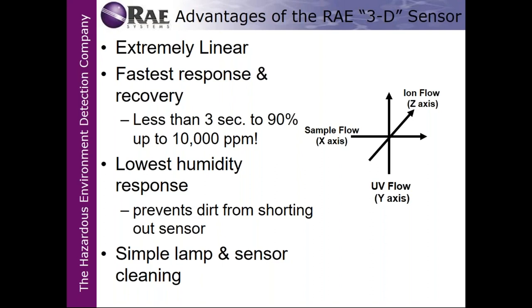We try to keep it as close as possible with not only a two-stage calibration, which would be your fresh air calibrate, and then you would have something for the low end, but you also would use a high end. In other words, in a MiniRAE 3000, you do a fresh air calibrate. You would calibrate to, let's say in this case, 100 parts per million, and then you can get a bottle of 1,000 parts per million. So it protects that linearity between 100 and 1,000 and tries to keep that linearity very close to 100% over 1,000, up to 15,000 parts per million.